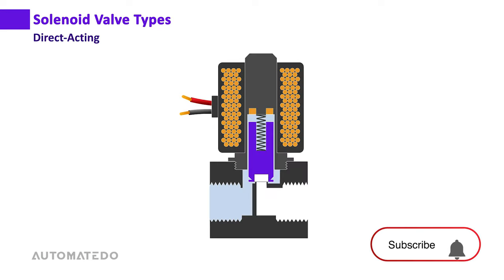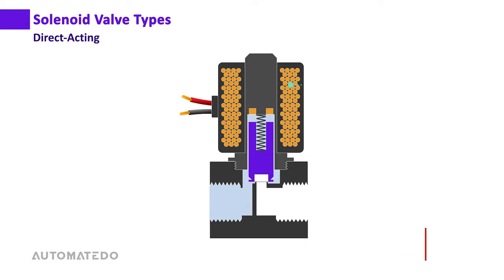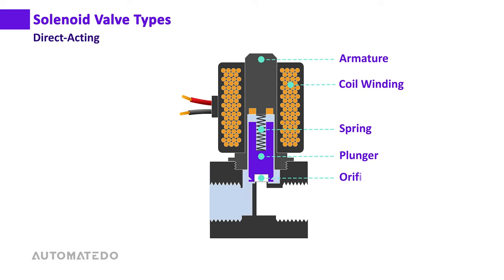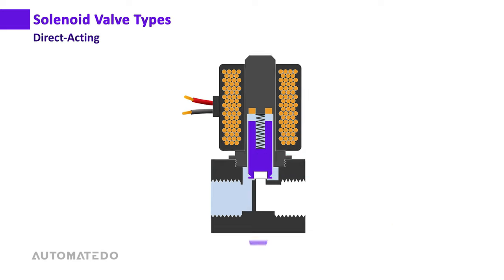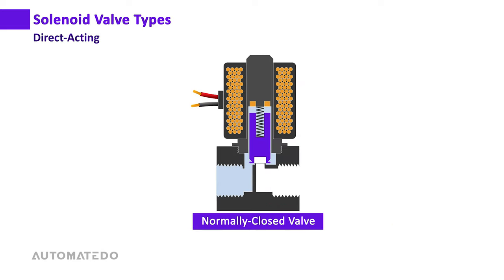The main components of the direct acting solenoid valve are the coil winding, armature, spring, plunger, orifice, and valve body. For a normally closed valve, in the rest position the spring pushes down the plunger to effectively block the orifice and prevent the media flow from entering.